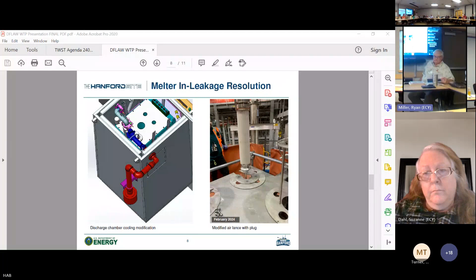If I confused it the way I said it, I apologize. The water chemistry of that liquid coolant was inconsistently controlled, meaning it wasn't always in spec, and they weren't always prompt getting it back into spec. They believe that contributed to some additional corrosion. There's also a belief there's probably some defect there. It's a straight part of pipe, not a weld, not an elbow. So it's believed there was some defect in that part of the pipe, which was then exacerbated by corrosion with the material inside. There isn't any belief that it was from heat outside or from the external air in that chamber.